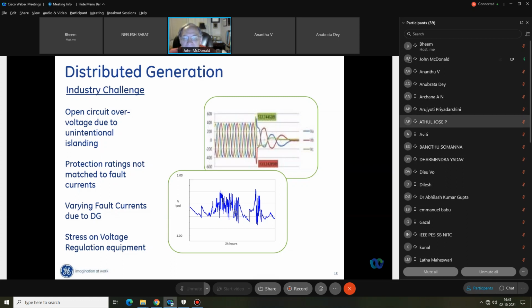When we do that short circuit study, though, we typically would only look for the contribution to the fault from the source side. We typically would not model the load side contribution. The challenge, though, is as the penetration of distributed generation increases, we will have a significant contribution to the fault from the distributed generation, from the load side. If we didn't model that when we determined the ratings of the protection equipment, then we may have protection ratings that don't match the fault currents. And this has been a problem.